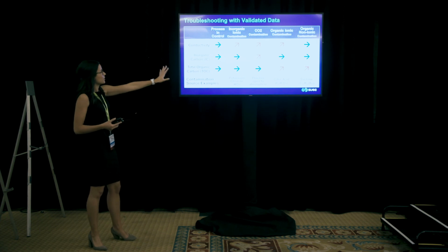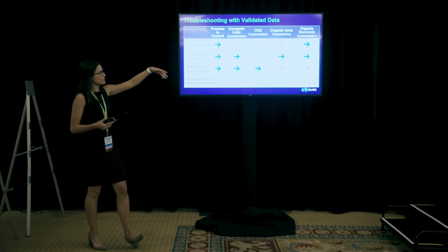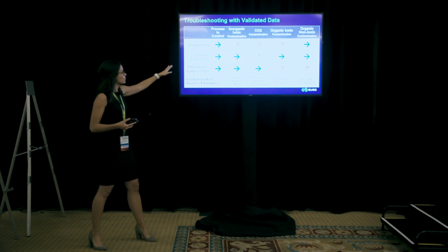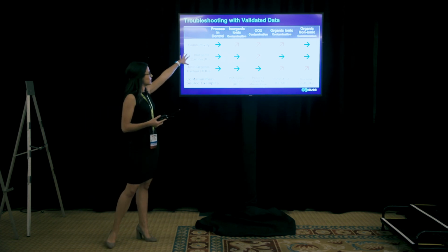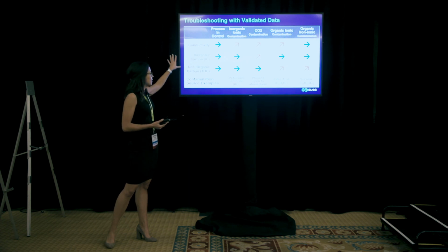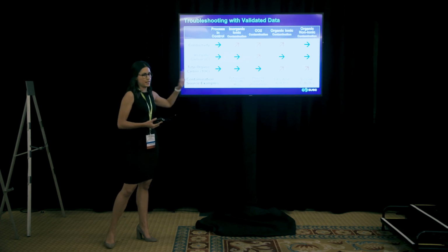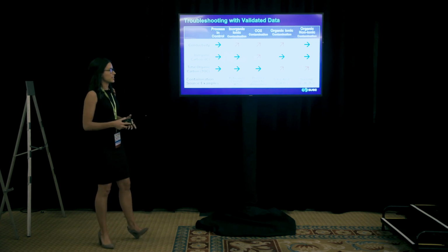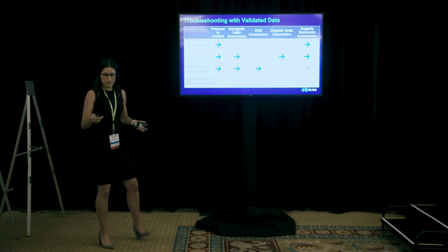The last one, like I said, sucrose isn't ionic and it doesn't create a huge response. So you might see your inorganic carbon and your conductivity are within their control range, but your total organic carbon is spiking. So it's important to have all 3 of those data points to really understand what's happening in your system.